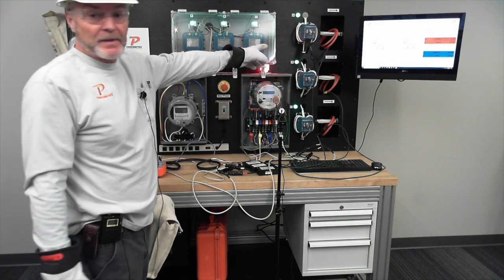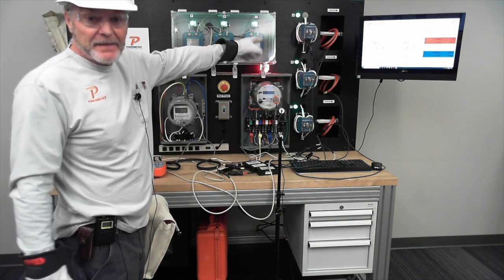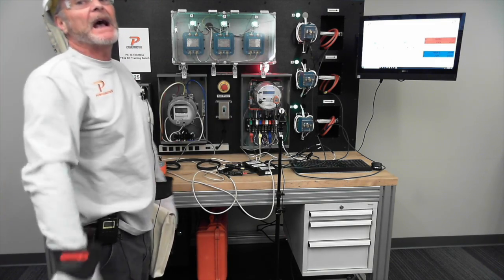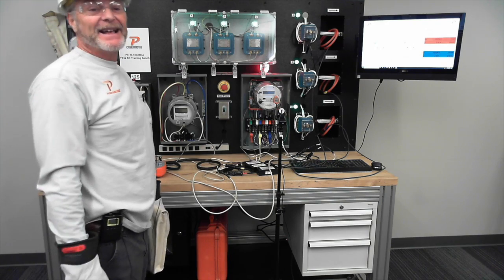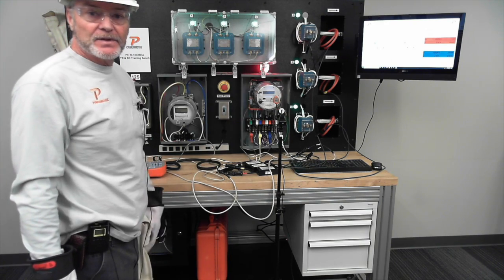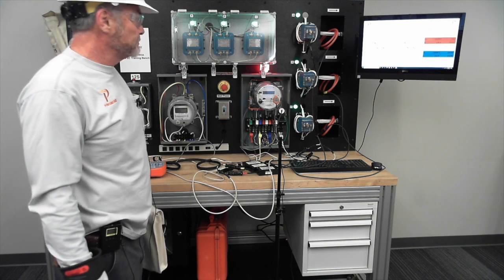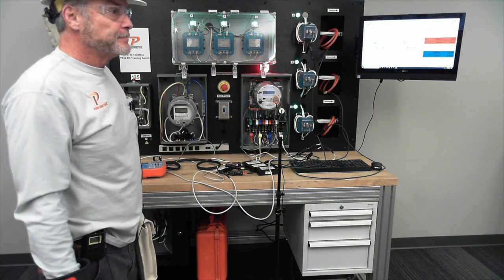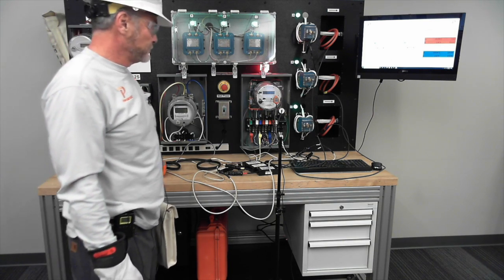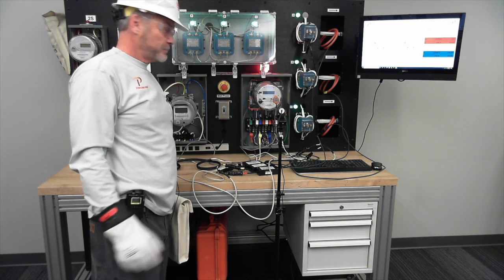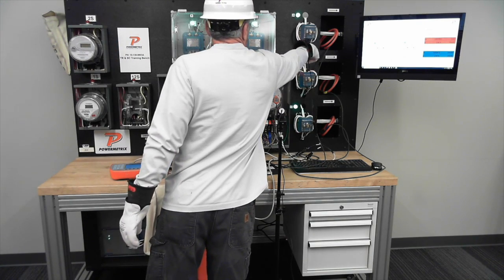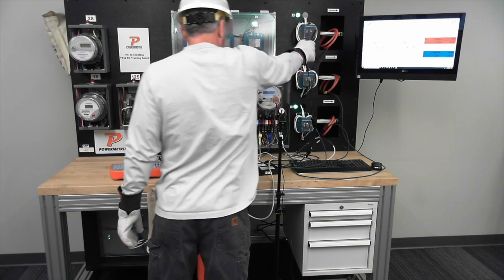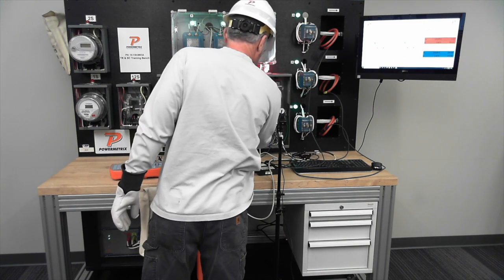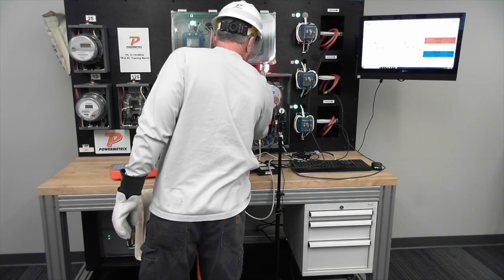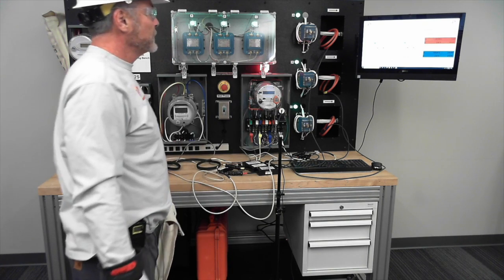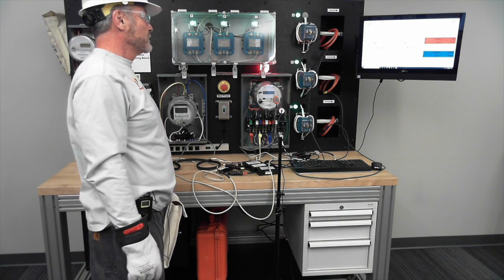Absolutely, and there are a lot of people that do this because it's a great solution if you think about it, than having to drag all that stuff out there and then drag and put all that stuff back. Yeah. And so this way you could just do it right there if you're just looking for a ratio on that CT. So the 2 cons I'll say of this is, again, you lose your burden. Mm-hmm. You cannot do a burden add test. Right. And you're losing the circuit between the meter and the CT. You're kind of shortening that circuit, I guess. Yes. Yeah. So you're not seeing that.